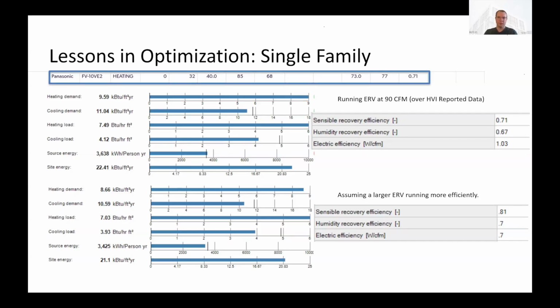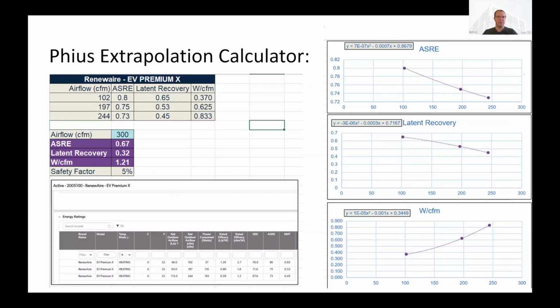Okay. There is one other little side note on this, that PHIUS has developed this calculator, and this is the example for the EV Premium X. They're still working on this a little bit, so I don't know if it's public. I couldn't find it publicly, but it gives you the ability to put in the data from HVI. So you can see in this case HVI rated this at 102 CFM, at 197 CFM, at 244 CFM. And because of that, we're getting down to a, then you can put your actual airflow in there and it will calculate what your efficiency is.